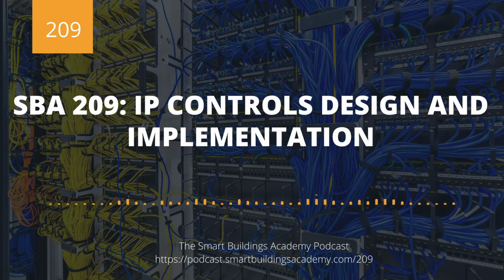Then from there, you actually have port security at the switch itself. You can ensure that the port is matched to a specific MAC address that is in that field controller. Granted, there is MAC address spoofing. You can also go and have MAC address duplication disabled or multiple MAC address disabled so that multiple devices can't connect via that port. There's a variety of things you can do from a port security perspective.